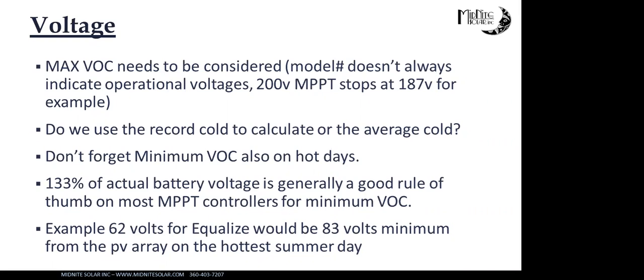The other thing to be aware of, and this gets missed a lot, is the minimum VOC for hot days. So, I probably should have started with this, but a solar module's voltage will fluctuate with temperature. So a module, if it says it's 44 volts open circuit, that's at standard test conditions of about 70-something degrees Fahrenheit. So as it gets hotter, the module's voltage will drop, or as it gets colder, the voltage will rise. So most of your MPPT charge controllers that are on the market today require at least 133% of the battery's voltage to actually wake up, and you leave them a little room to work.